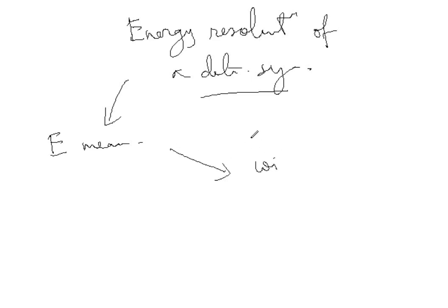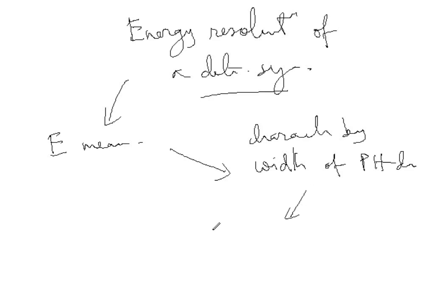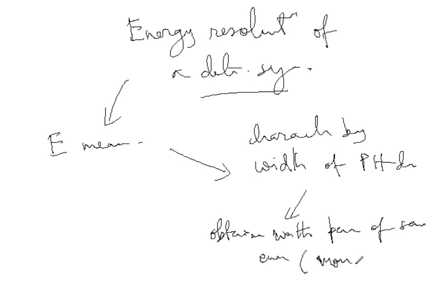So this is characterized by width of pulse height distribution, and this is obtained with particles of the same energy, or monoenergetic source basically.